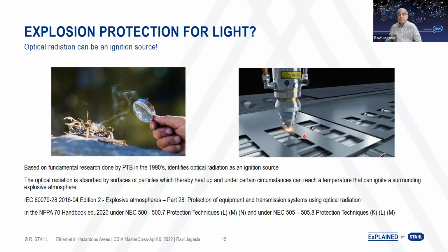One of the elements of what you saw earlier when I showed Ethernet with fiber optics was how could I run fiber optics in the hazardous area? And why is fiber optics, or optical radiation, an ignition source? I hope you all remember there is a famous triangle, not the Bermuda Triangle, but the famous triangle for explosion protection, or why an explosion occurs. It is the ignition source, the fuel or combustible mixture, and then of course oxygen. And how optical radiation became a source for ignition.